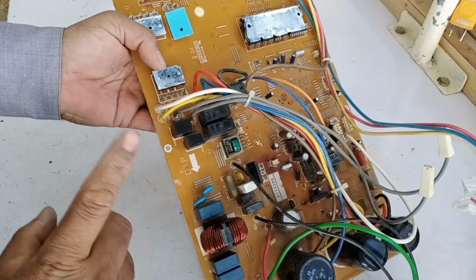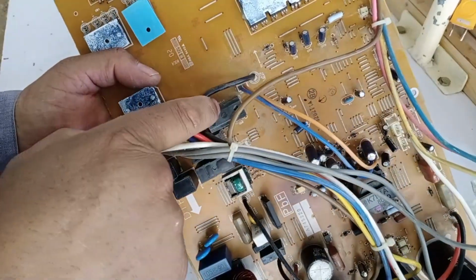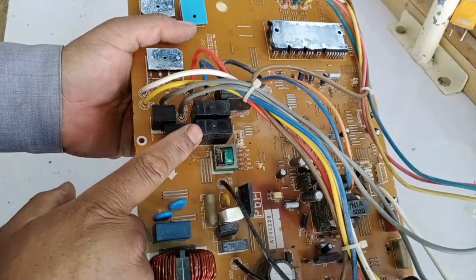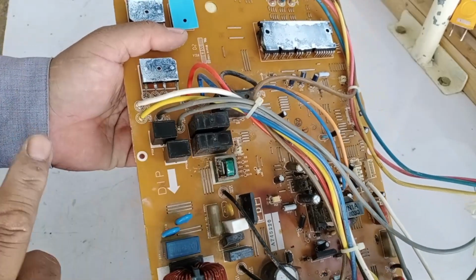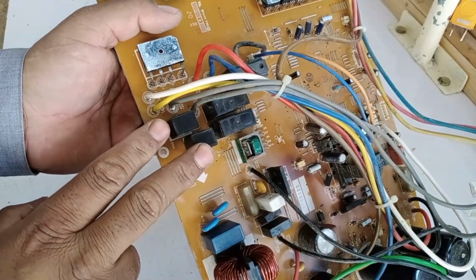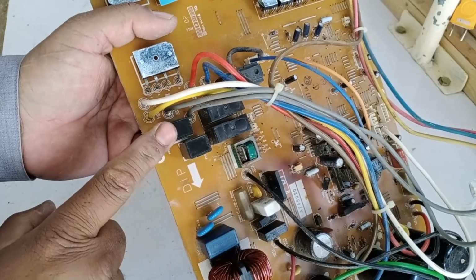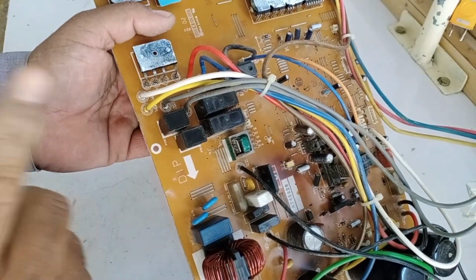fluctuations. Now, as you can see, 3 switching relays have been used in this PCB. The reason for this is that it's a larger outdoor unit, which requires 3 relays to handle the load effectively. Additionally, 2 PTC sensors have been installed. Now, I will explain what has been done.